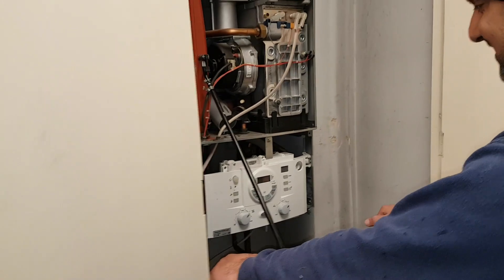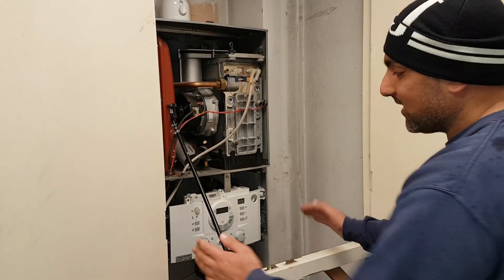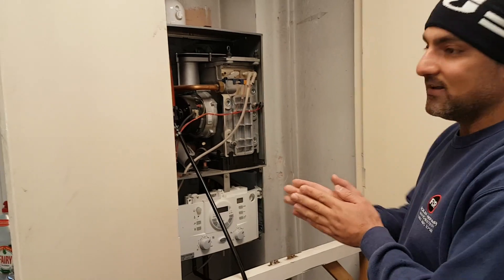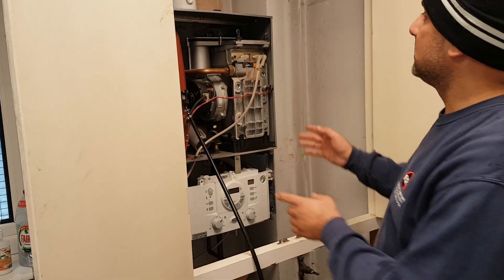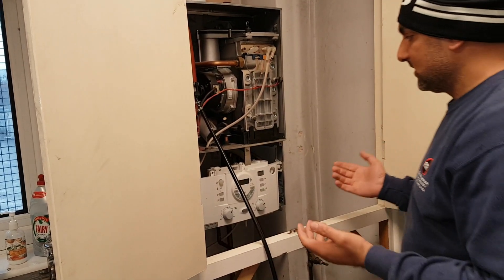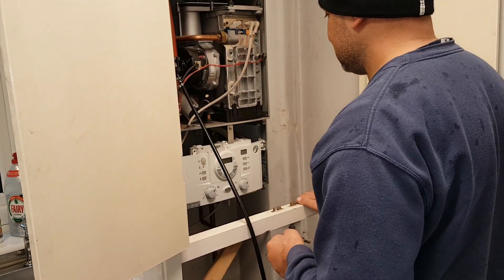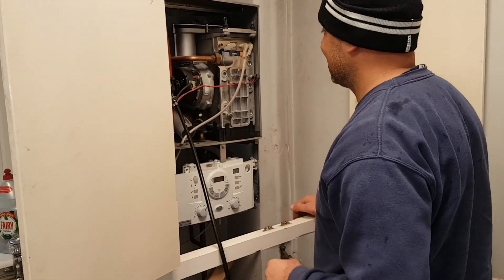How did making that decision make you feel? In the classroom it was straightforward, but right now I had to think about it — is there an upstairs? We don't know, it's a commercial unit, there could be. But when you look at the pipework, there's nothing going upstairs apart from a gas pipe going down. You've done a good call. It's your second boiler — that's good, it's part of your journey and learning.